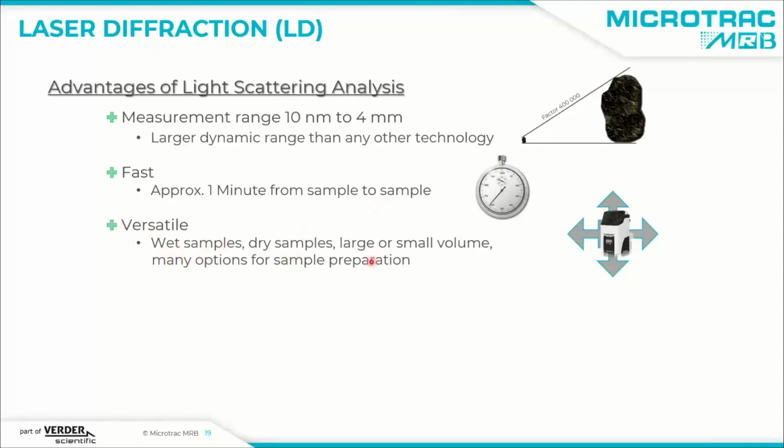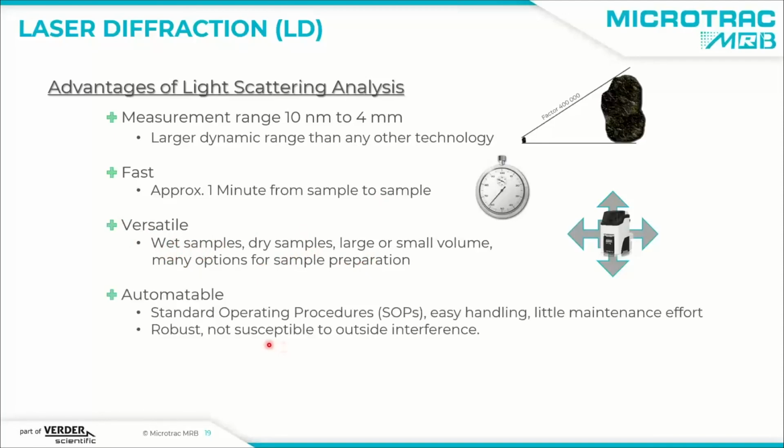So you can do wet or dry analysis. You have many options for sample preparation. It's highly automatable. You can use standard operating procedures. You have easy handling, little maintenance effort, and it's very robust and not so susceptible to outside interferences like vibration, temperature change, contamination of the liquids. So all this can be handled by the analyzer and does not affect your results very much.